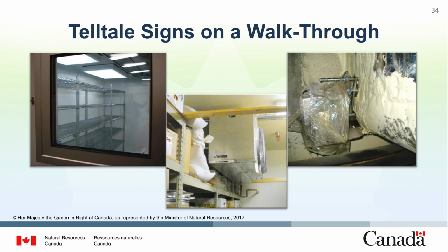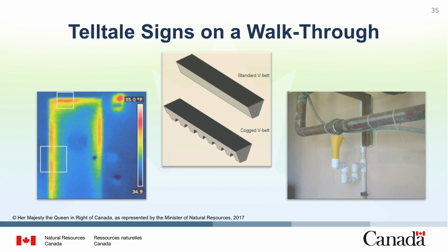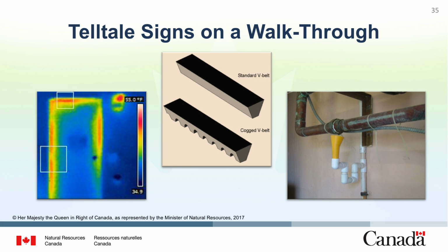Next, we walk into the cafeteria area and decide to look above the ceiling. Here, we see a fire damper that is still wrapped in its plastic. We learn that it's been like this for 7 years and it was never commissioned. So we point this out to the facility staff and they assure us that it will be taken care of. Also in the cafeteria, we look at the walk-in coolers and freezers and can see from the infrared image that there's an opening that needs to be sealed.